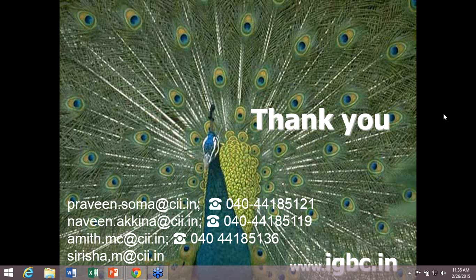In homes, irrespective of whether it is a centralized AC or non-air conditioned building, if it is a non-AC building, that means even though it has a unitary AC, it can be a VRV system or it can have split units, projects need to provide a fresh air opening in their living spaces. We consider a building fully air conditioned only if it is centralized AC. If it is not a centralized AC, projects need to meet the thresholds mentioned in the fresh air ventilation criteria.